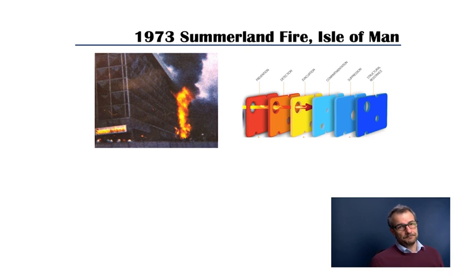Evacuation was breached as well, in the sense that evacuation was not well organized. It was not coordinated. People were not clear how they had to evacuate. The layout of the building was in different stories with mezzanine and open spaces. People were not clear how to evacuate. Parents realized that they were not going to evacuate without their kids, who were in a completely different area, and they had to cross the paths of evacuation. It didn't go well.